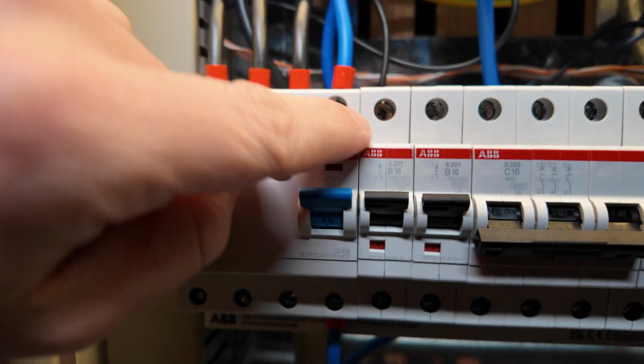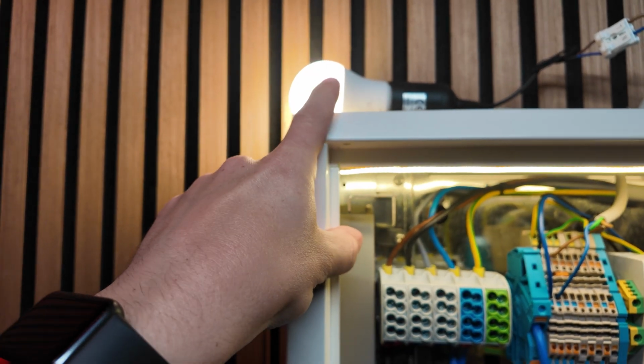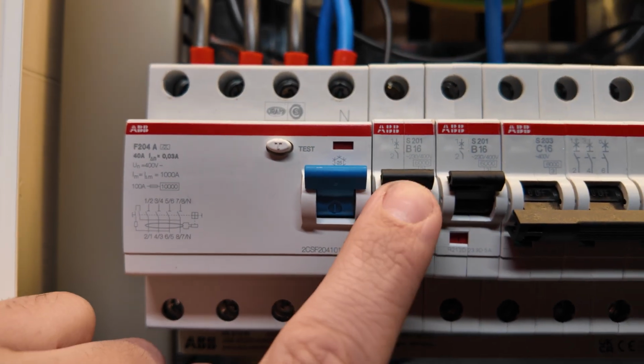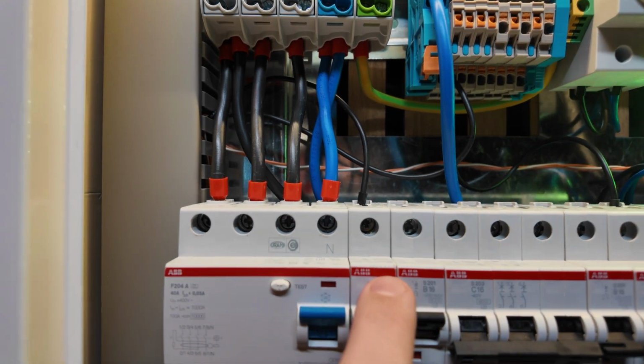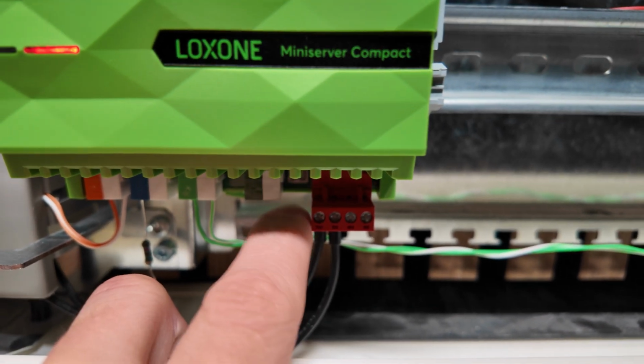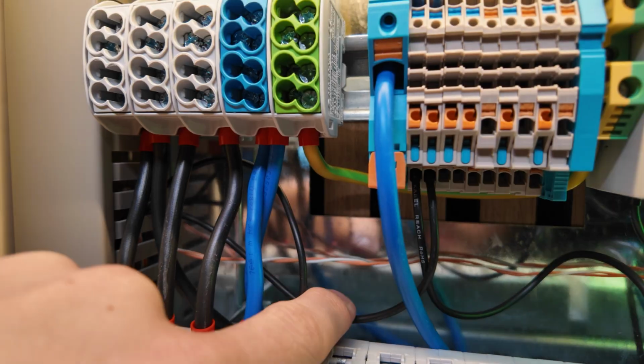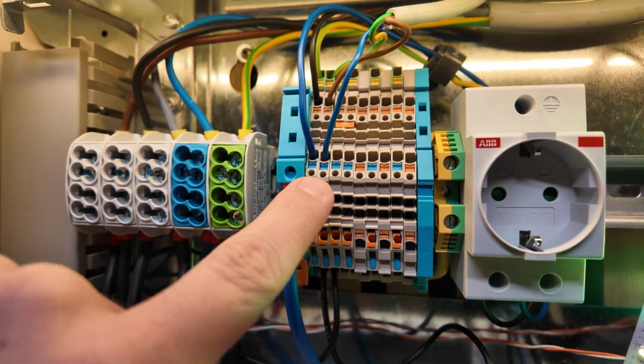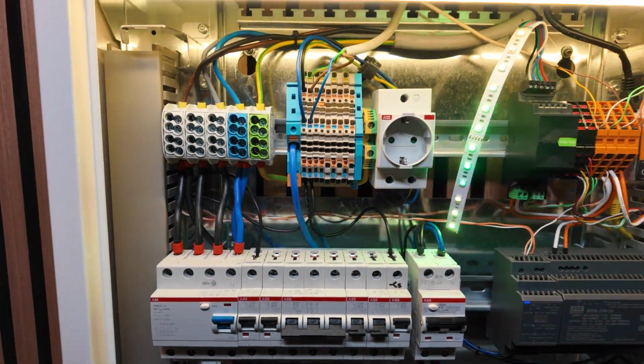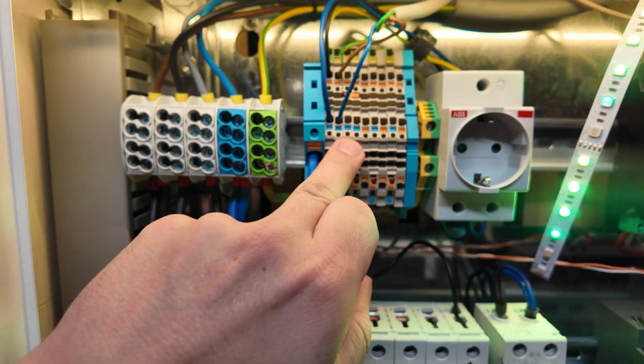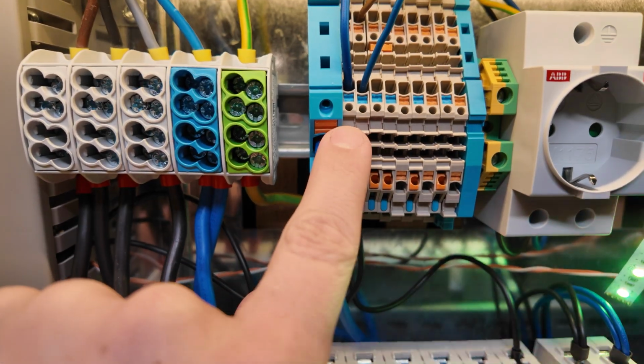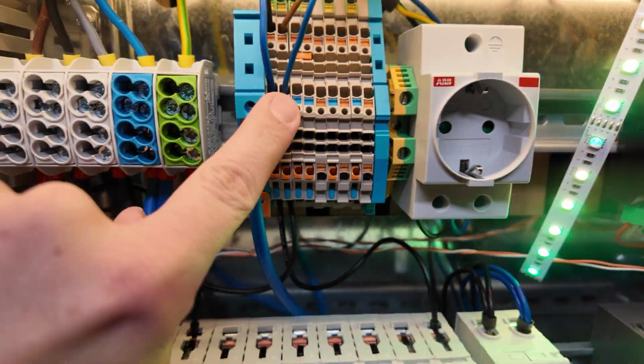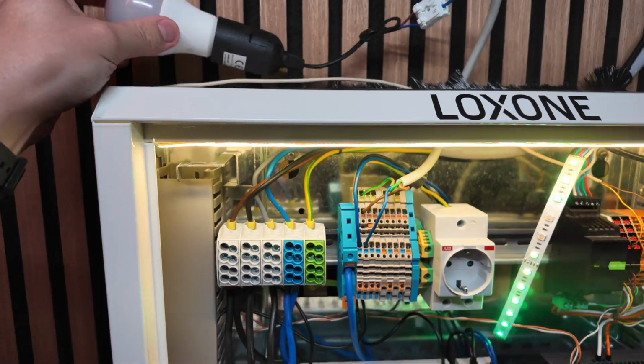I am going from this breaker here, and that's important. If you say, okay, this lamp is in the living room, then I would also take care that the breaker which is used for this lamp is also for the living room. So I go from this breaker here, the first one, I go down to the relay's input here, and when the relay is switched, I go back up, and then this goes to the lamp. And I'm using terminal blocks here as well, because as I said, I love them. These are from Weidmüller as well. It makes life so much easier for me, because then I can build cabinets nicely in the workshop, in the office, and then I can deliver them on site, and then you only need to connect the cables. There are labels as well. And then it's like terminal block number 1 equals sockets, then terminal block number 2 equals this one here, which goes to the lamp.